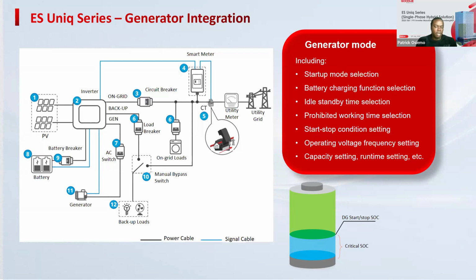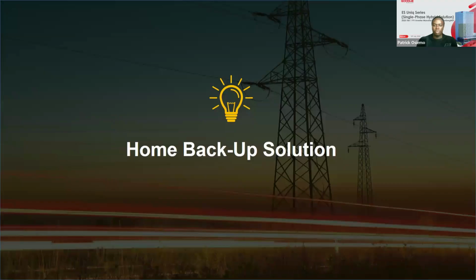It's very much smart to the point that you can use the inverter with new generators and old generators simply because you can also edit the voltages and frequencies that come from the generator. I mean, the voltage and frequency that the inverter can accept from the generator. So that's how much we are very integrated with the systems right now residentially. So PV and diesel generator integration achievable with the ES Uniq.